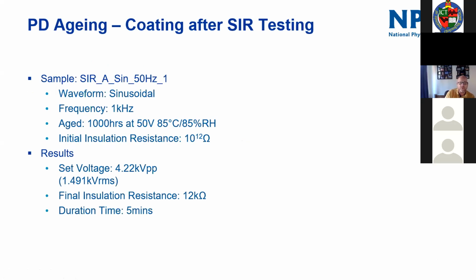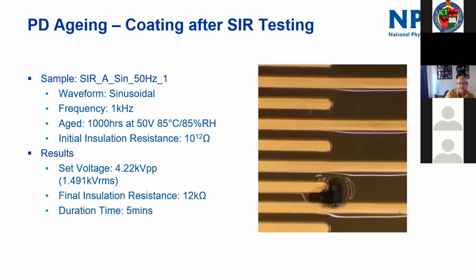So what we then did was run a simple sinusoidal test, 1 kilohertz at 50 volts. The sample had already been aged for 1,000 hours, but we didn't see any surface insulation resistance. We ran it at 4.2 kilovolts peak to peak, which is just under 1,500 volts RMS on a sinusoidal waveform. And that's what happened after 5 minutes.